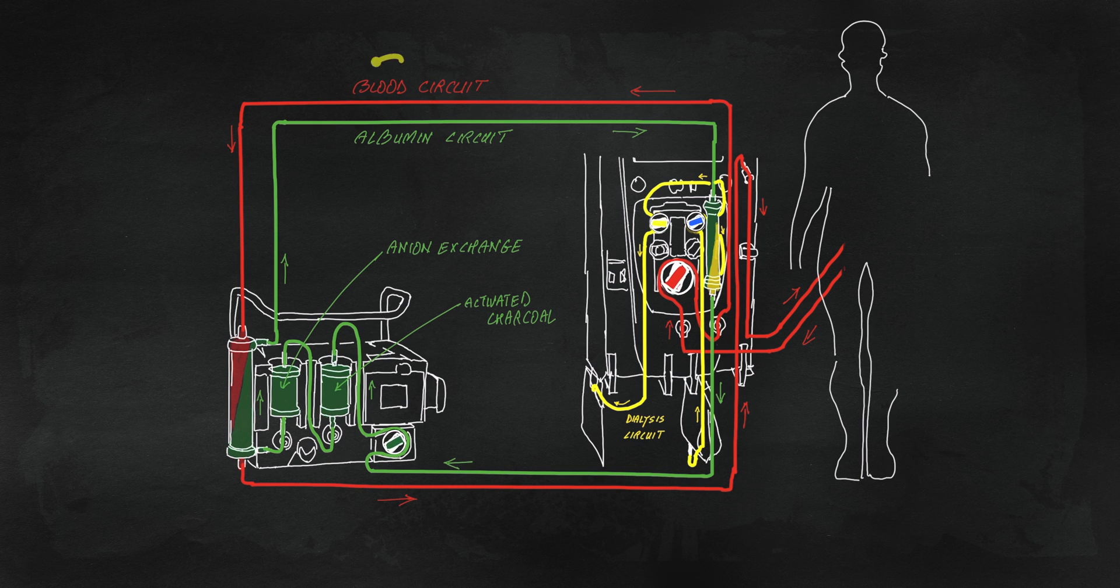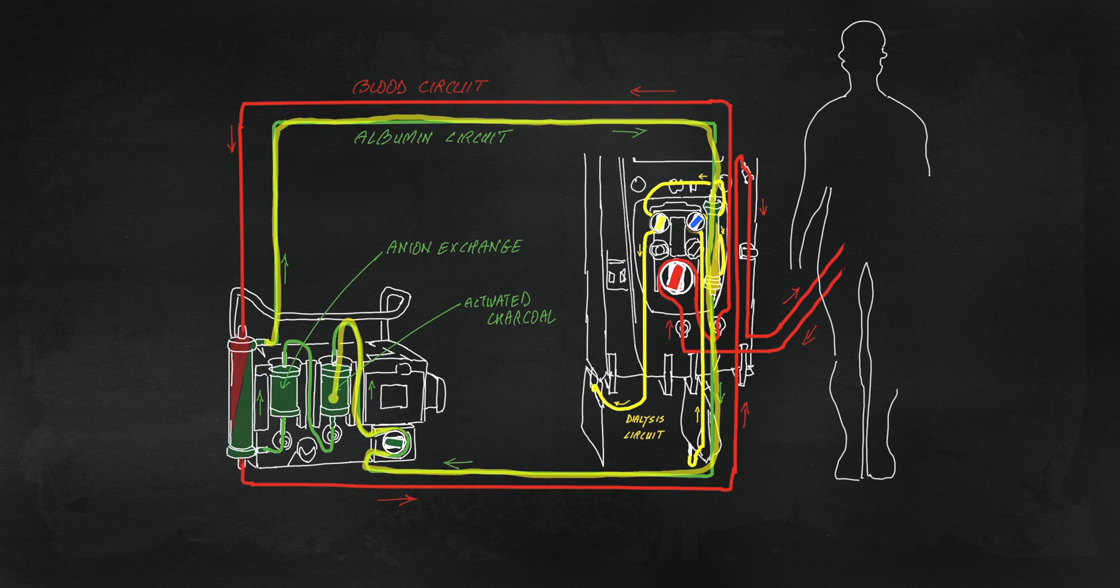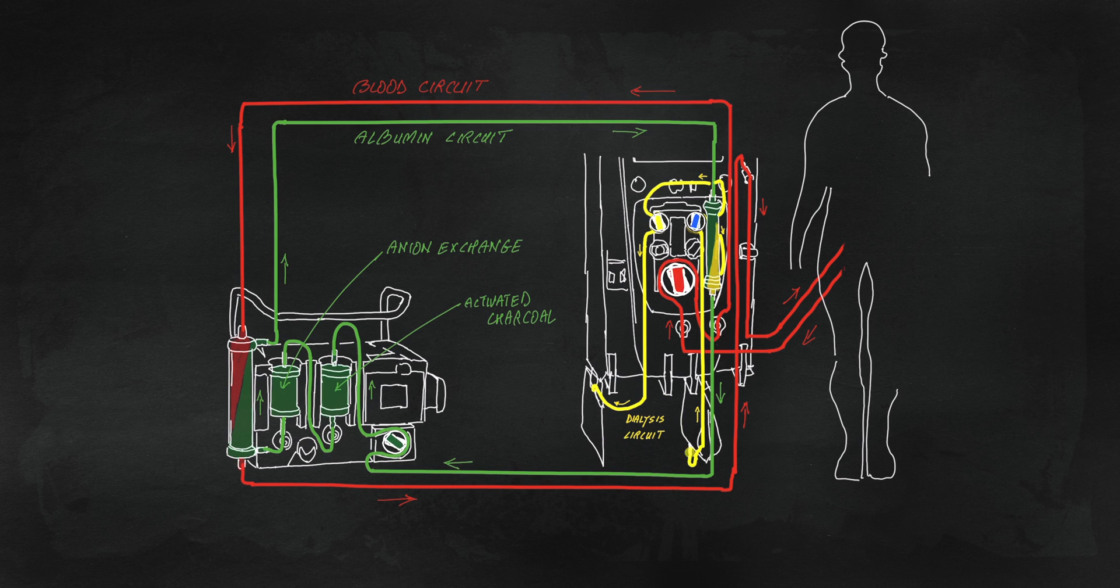To recap, we have the blood circuit, driven by the PrismaFlex blood pump. The closed albumin circuit, which stays in motion via the pump on the MARS machine and goes through all the four filters. And last is the dialysate circuit, which clears the albumin circuit from typical low molecular weight and non-protein bound solutes such as electrolytes, urea, creatinine, and ammonia.